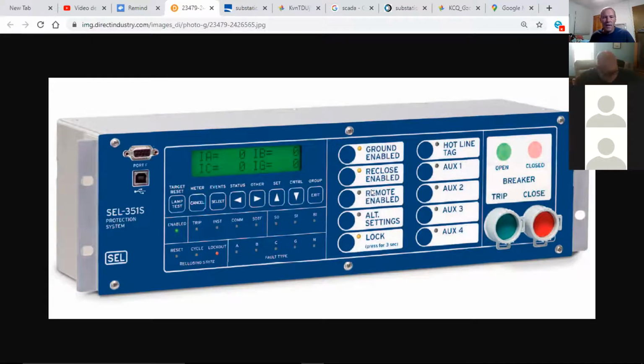This is already in local because I have no light. Say it's lit up, I press it, they're going to get an alarm in the dispatch center. It's going to say Surfside A is now in local. When I say alarm, alarms would be going off all day long, wouldn't they? It's just a ding ding. And it's going to prompt them on their screens. Remember that control center that I showed you? It's going to prompt them on their screens, Surfside A is now in local. All right, obviously, if it happens and you have not contacted the dispatch center, they're going to have some questions, or they're going to start calling somebody, hey, Surfside A just went to local. You're going to have to communicate with the dispatch center before you do anything on this.